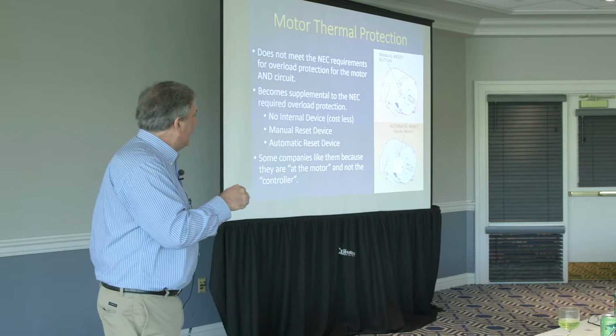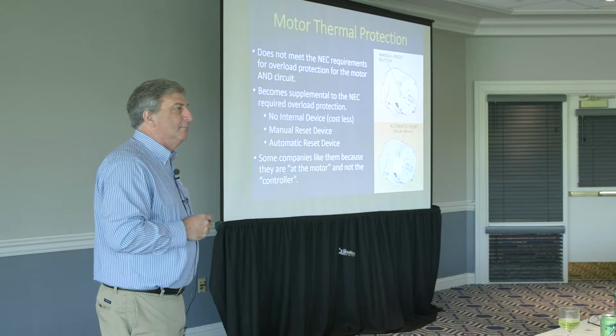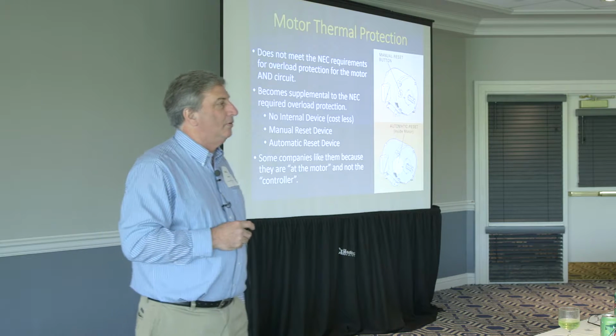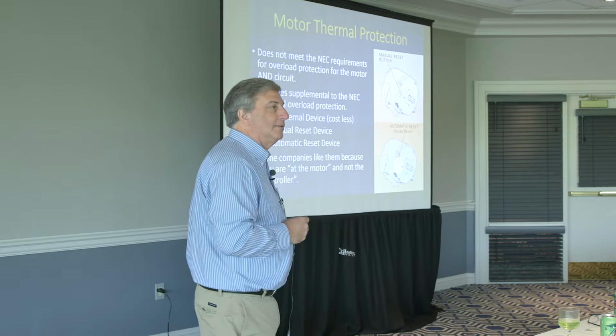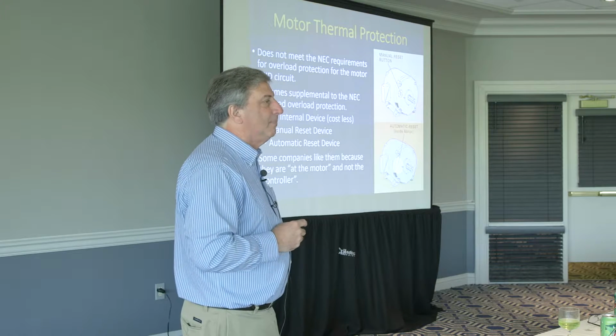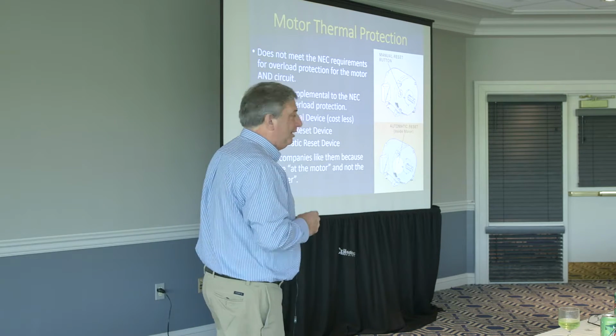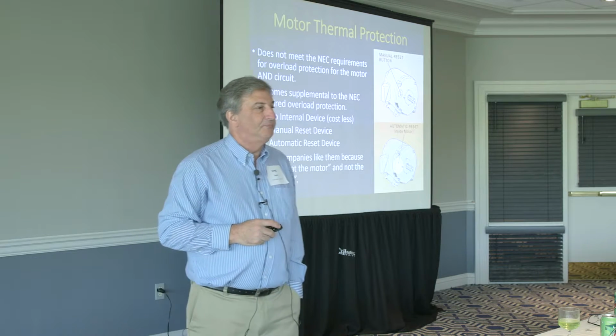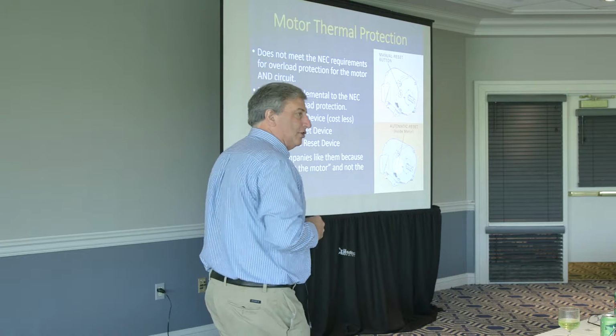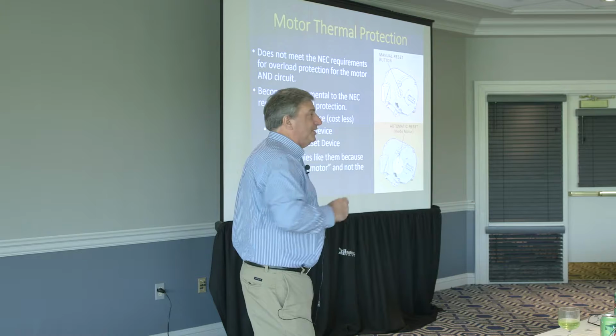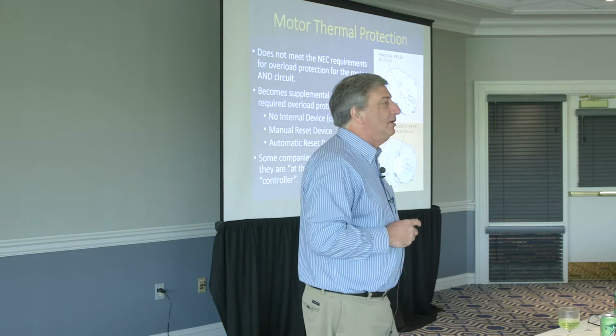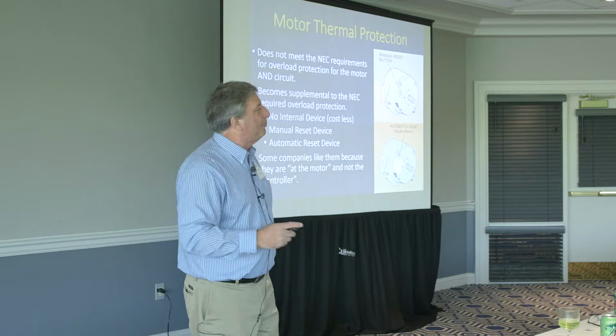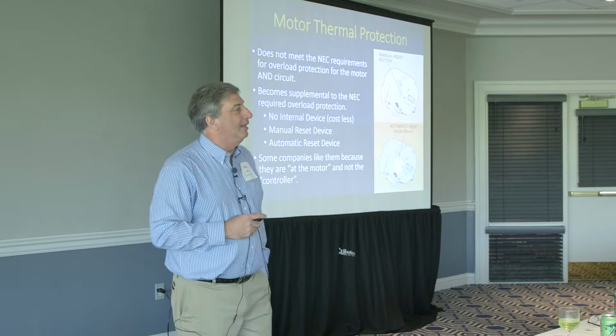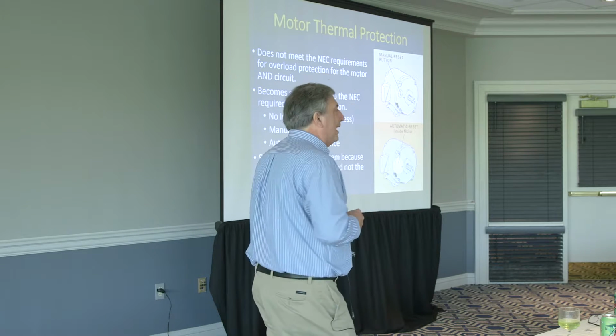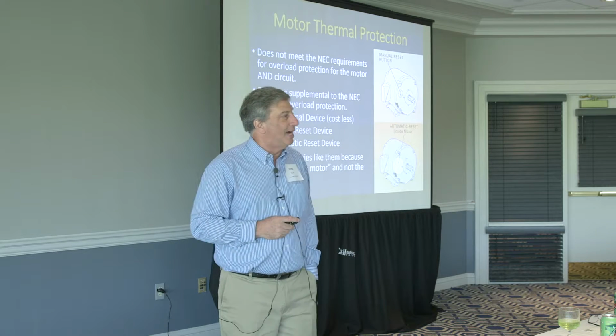So now, what's an implication in using a motor with an automatic reset in the motor for overload? What if I'm using two-wire control? I have a float switch or a thermostat, turning that motor starter on and off. And the overloads in the starter panel don't trip out, but this overload trips out. At what point does a person, subcontractor, or young person in your plant, because they see the contacts in that float switch or that thermostat should be closed and the motor's not operating, assume the power's off and violate lockout tagout procedures and now start messing around with the system without ensuring the power is off?